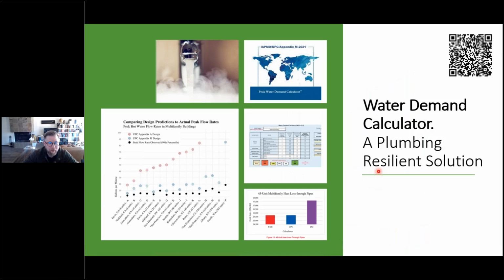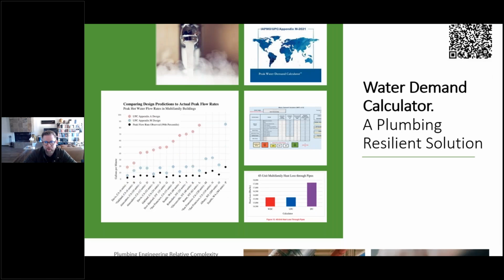I'd be remiss if I didn't talk about right sizing. As we mentioned before, the larger the pipe, the more heat dissipation. And so if you reduce your supply pipe size, like using the water demand calculator, which would be approved for multifamily buildings, let's say, and we're working on the commercial sizing for healthcare, hospitality, offices, schools, and the like. By reducing your supply size, you're not going to need as much flow through your return side. So it's definitely worthwhile right sizing your system. And there's the QR code if you want to get to the IAPMO water demand calculator webpage.